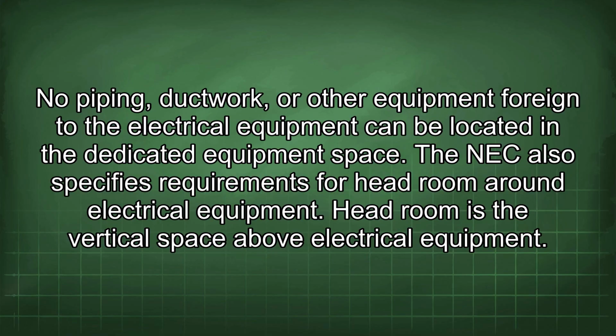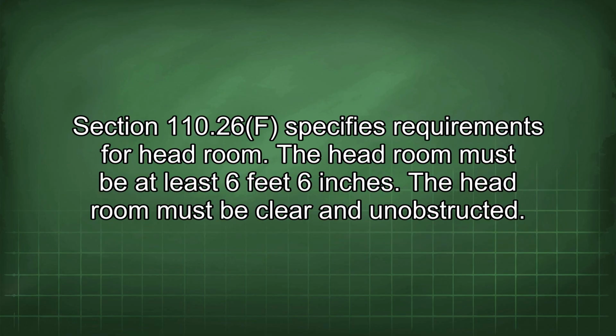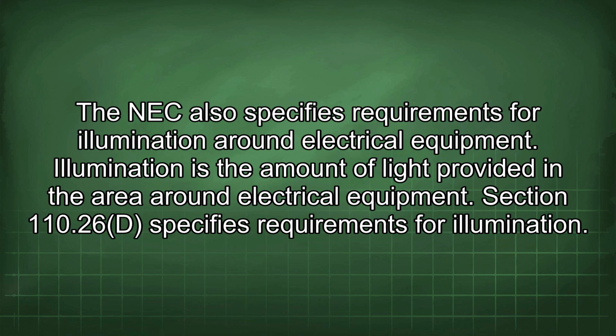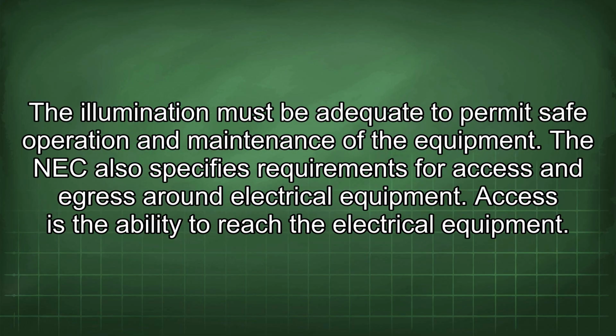The NEC also specifies requirements for headroom around electrical equipment. Headroom is the vertical space above electrical equipment. Section 110.26(F) specifies requirements for headroom. The headroom must be at least 6 feet 6 inches. The headroom must be clear and unobstructed. The NEC also specifies requirements for illumination around electrical equipment. Illumination is the amount of light provided in the area around electrical equipment. Section 110.26(D) specifies requirements for illumination. The illumination must be adequate to permit safe operation and maintenance of the equipment.